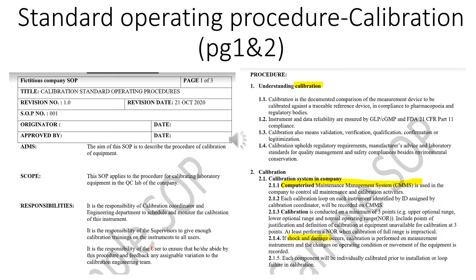So other than the headings and writing down the definition of calibration, and also introducing the system used electronically, the CMMS, it is also important to write down the instrument specification. This is just a very broad one, so it doesn't specify which instrument. For some instruments, it might be important to write down what instrument it is, the model, the make, and what the calibration is, followed by the manufacturer's instructions. So there are a few things to be written down.